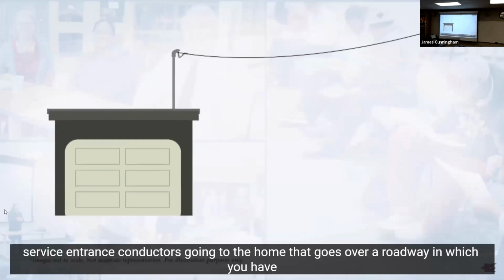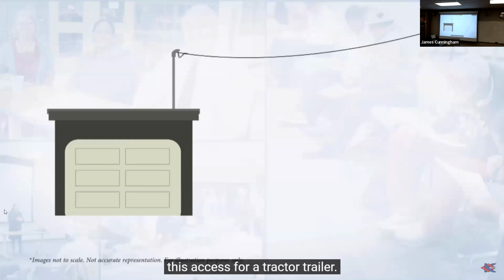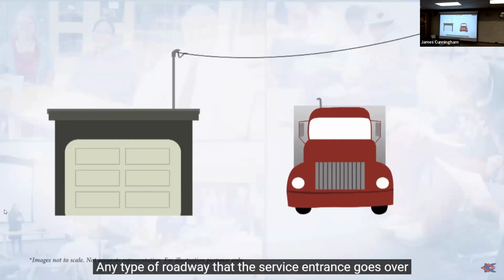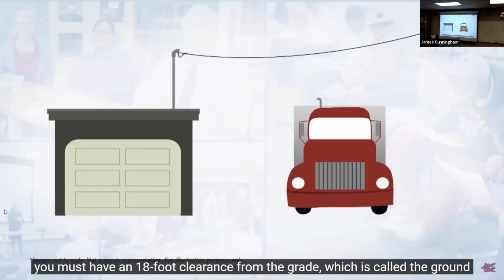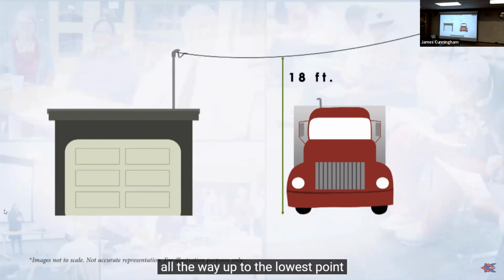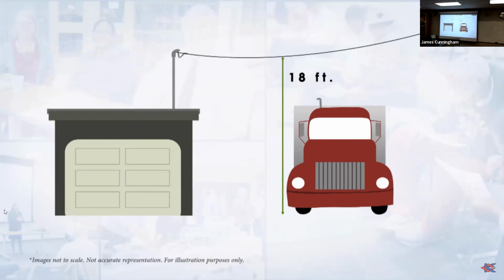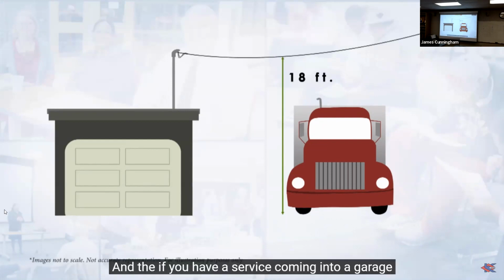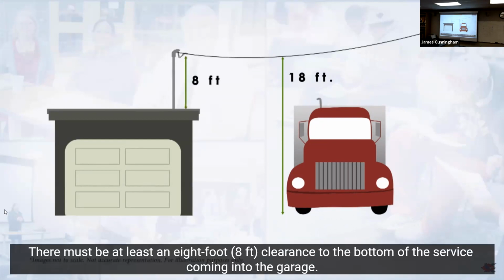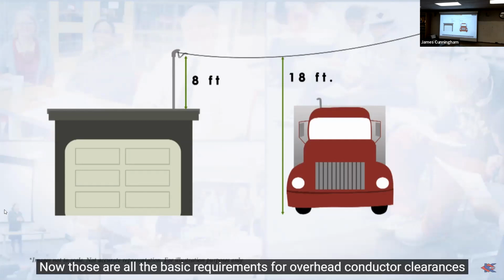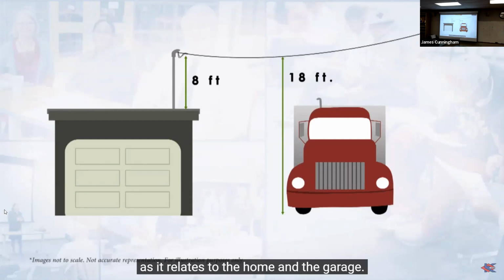The next portion of this National Electric Code that is showing you is service entrance conductors going to the home that goes over a roadway in which you have this access for a tractor trailer. Any type of roadway that the service entrance goes over, you must have an 18-foot clearance from the grade, which is called the ground, all the way up to the lowest point on the overhead feeder. And then if you have a service coming into a garage, and the garage has a flat roof on it, there must be at least an 8-foot clearance to the bottom of the service coming into the garage. Now, those are all the basic requirements for overhead conductor clearances as it relates to the home and a garage.